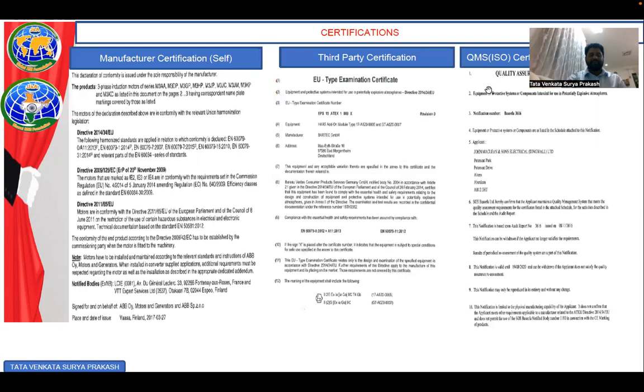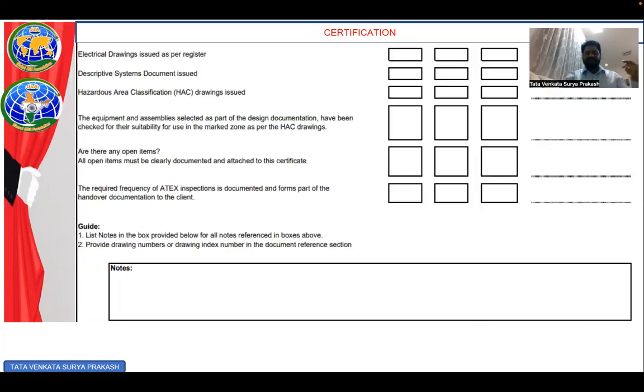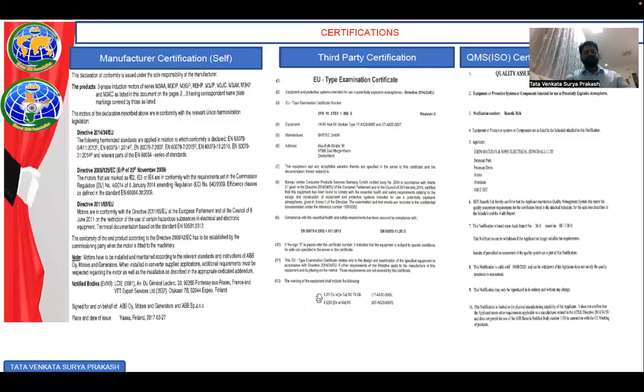The required frequency of ATEX inspections is documented and forms part of the handover. Once the vessel is manufactured, it generally has a long duration time, but periodically these vessels or ATEX rated equipment need to be inspected, because of corrosion over the design time. Corrosion allowances etc. are followed for a certain area, but based on operational conditions, exaggerated corrosion may lead to damage to the equipment.